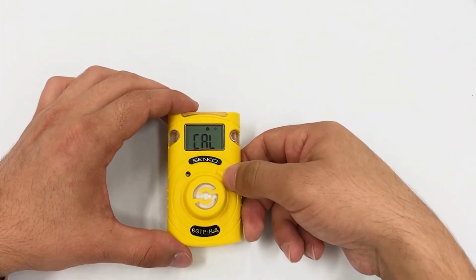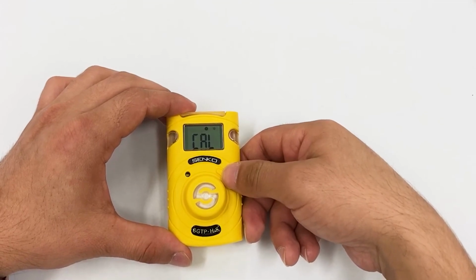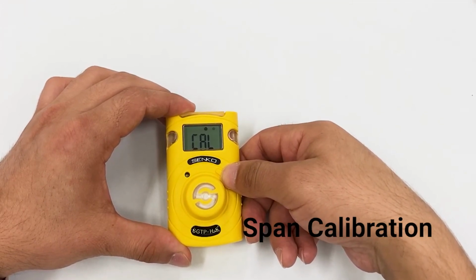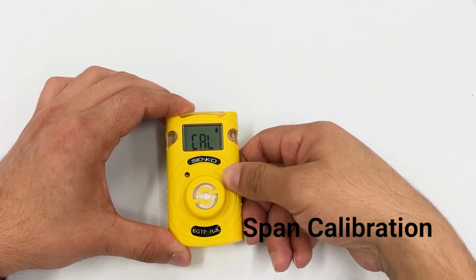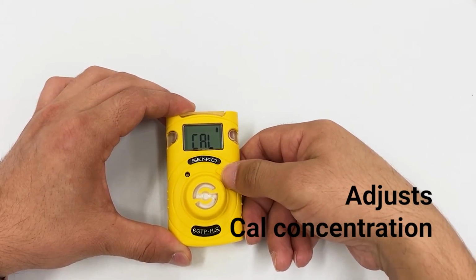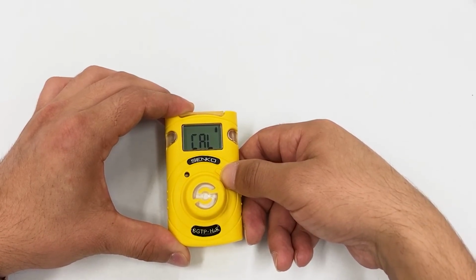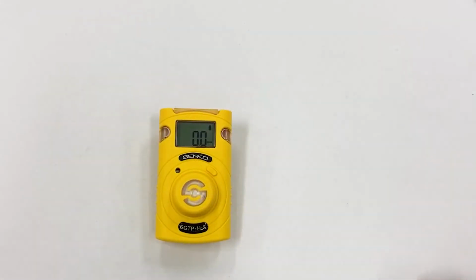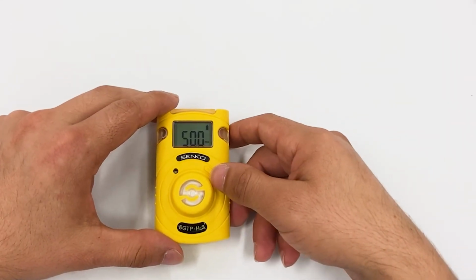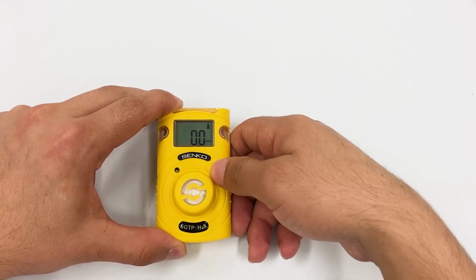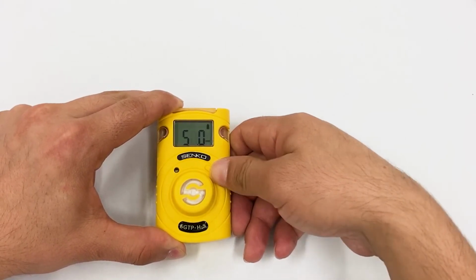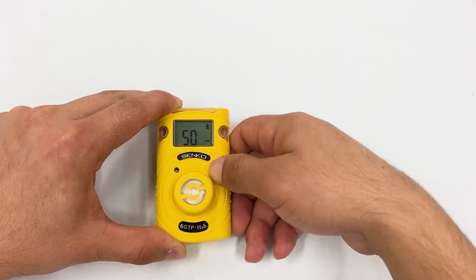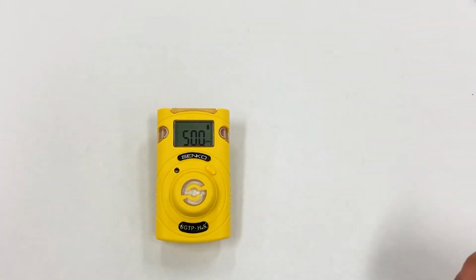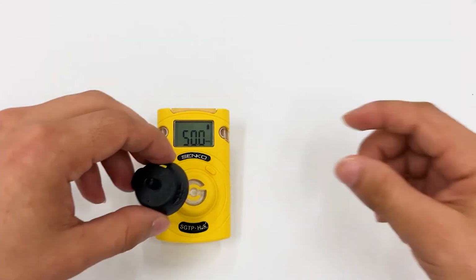So once the zero calibration is complete, you will be given the option to do a full span calibration. So if we just skip over, we will have an option to adjust calibration concentration of the device to be equivalent with our current can gas. We strongly recommend you to use equivalent gas concentration with Senko standard calibration concentration of the device. When adjustment is finished, we can apply the calibration cap and press and hold the button and open up our gas.